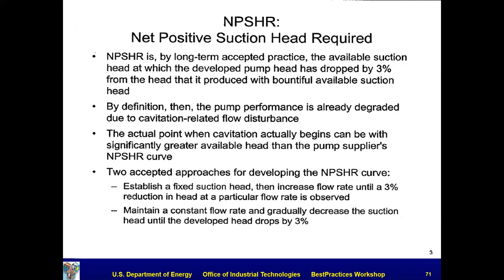Now, sometimes you've got to do what you've got to do, but you need to be aware of that. So when you look at those pump curves and it has that NPSHR curve on there, and you take your flow rate up and over and it says 20 feet, you have to realize that you're already slightly in cavitation if you just provide 20 feet. By definition, the pump performance is already degraded due to cavitation-related flow disturbance. The point when cavitation actually begins can be with significantly greater available head than the pump supplier's NPSHR curve. And then there's a comment there about measurement approaches, which I don't really care about.